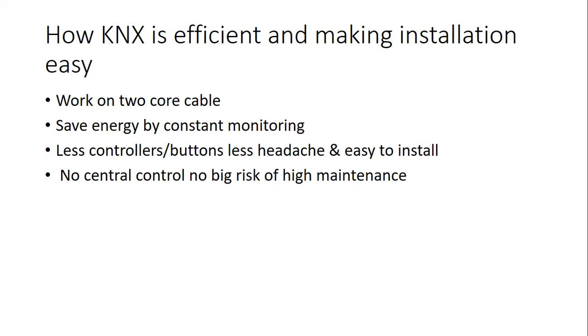You can have one controller or push-button switch that handles all your lighting in a specific area, create scenes, and that saves a lot of cabling — you just need a two-core cable to each device. There is no central controller, so there's no big risk of high maintenance. With other building automation protocols, if the central controller fails, maintenance becomes very costly. In KNX, each device is independent — if one device fails, you just swap that one device.